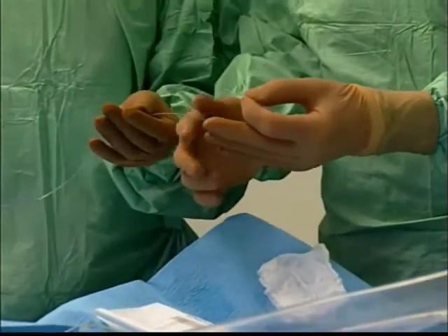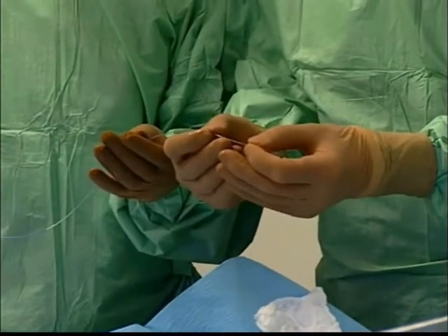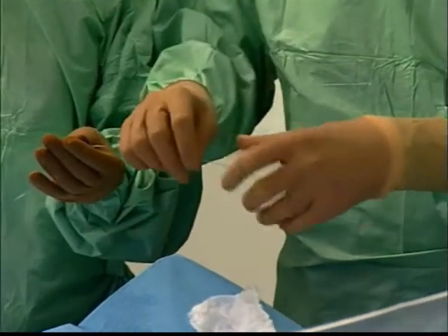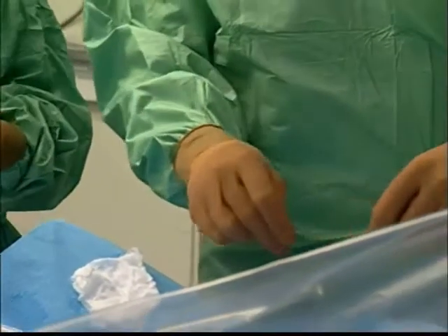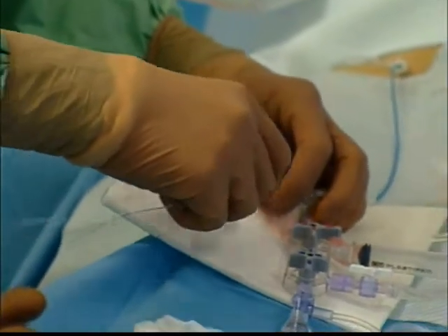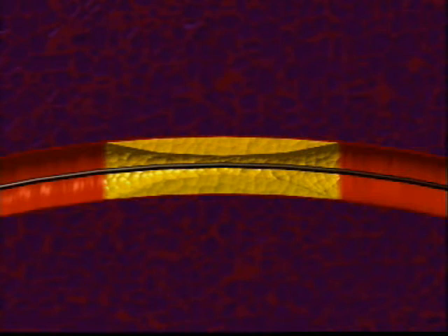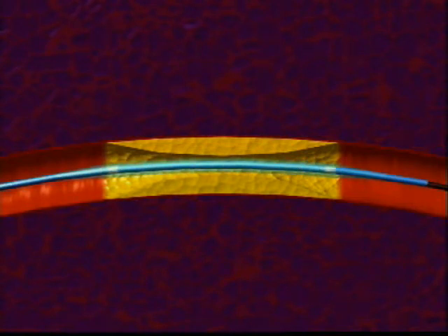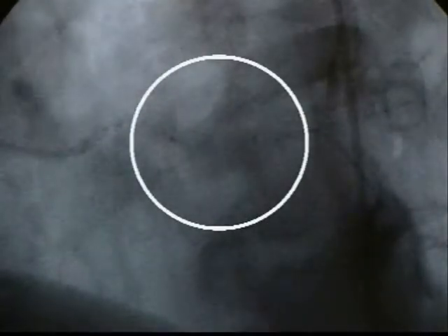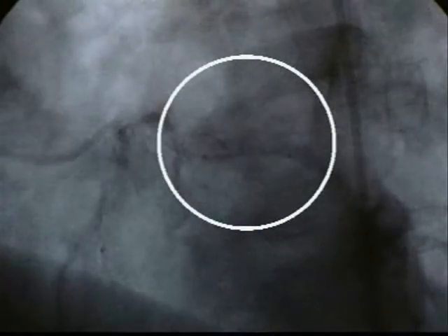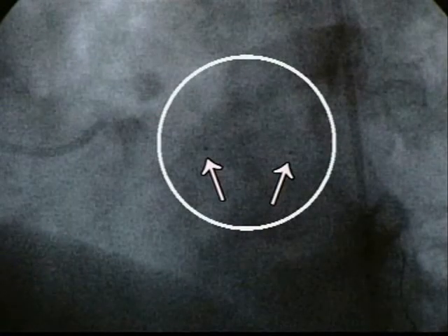The balloon is 10 to 30 millimeters long and 1.5 to 4 millimeters wide, and has been specially chosen by the doctor as it best suits the diameter and length of the narrowing being treated. Each balloon is made of special materials that allow it to inflate to a specific size. By monitoring the procedure on the monitor, the doctor positions the radiopaque marker bands. The marker bands indicate where the otherwise invisible balloon is.